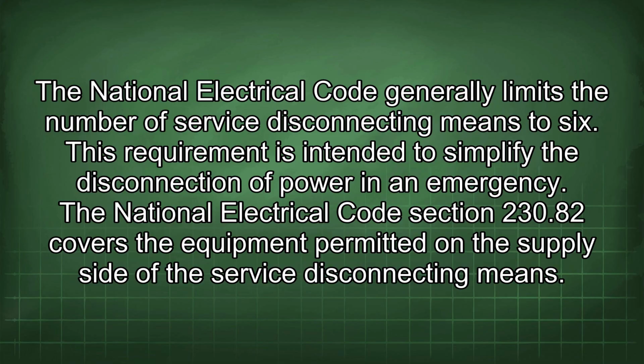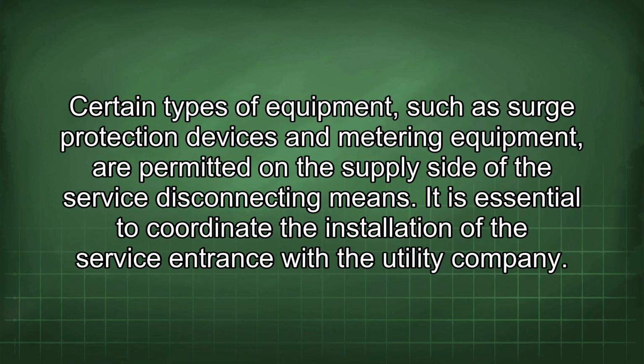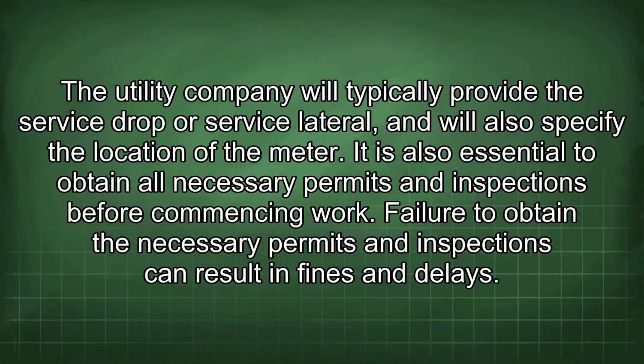The National Electrical Code Section 230.82 covers the equipment permitted on the supply side of the service disconnecting means. Certain types of equipment, such as surge protection devices and metering equipment, are permitted on the supply side of the service disconnecting means. It is essential to coordinate the installation of the service entrance with the utility company. The utility company will typically provide the service drop or service lateral and will also specify the location of the meter. It is also essential to obtain all necessary permits and inspections before commencing work. Failure to obtain the necessary permits and inspections can result in fines and delays.